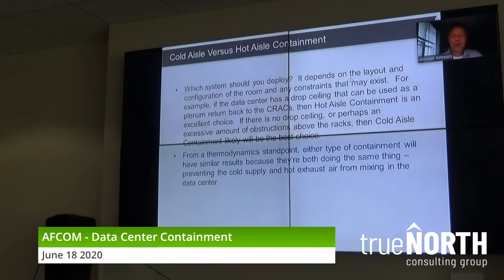For instance, maybe it's a raised floor, there's no drop ceiling. Maybe there's a drop ceiling, but there's so many overhead constraints. I'm going to probably suggest cold aisle containment in that case. Hot aisle containment, you've got a drop ceiling, it's not too high, it's easy to get the air back. It's plenum rated for a fire, et cetera. Hot aisle containment is going to be a great choice. Here's my point. From a thermodynamic standpoint, that second bullet point, it doesn't matter. Either type of containment is going to have similar results.